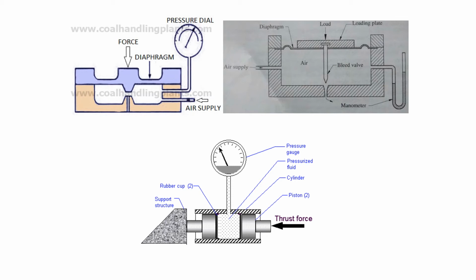So the load is applied. The bleed valve will close the container. By means of the manometer, we can measure the pressure also. This is another way of measuring the pressure. In the third diagram, we can see how the thrust force is applied and how the pressure is recorded on the pressure gauge, because of the compressible pressure acting on the cylinder. So these are the various ways and methods of measuring force acting on the substance by using air as the medium. That's why it's called a pneumatic load cell.